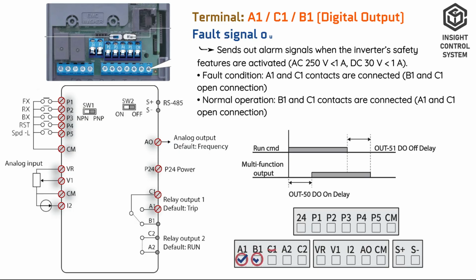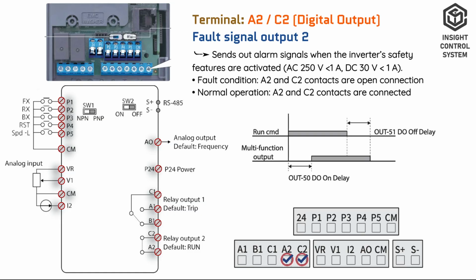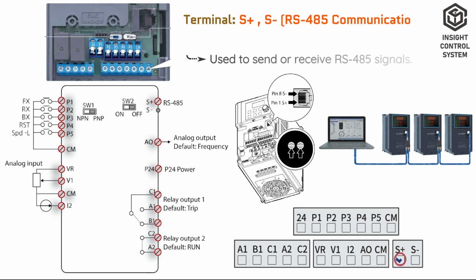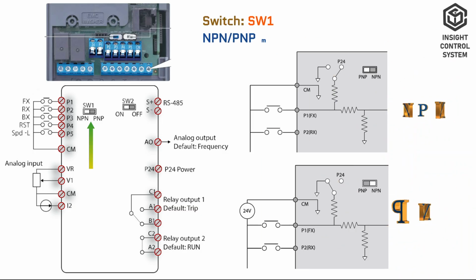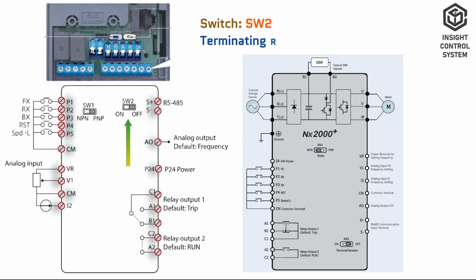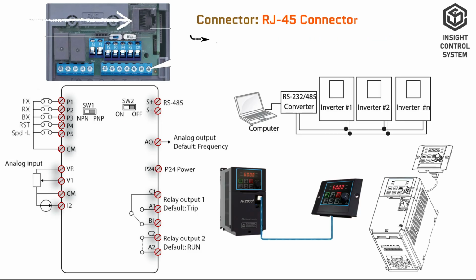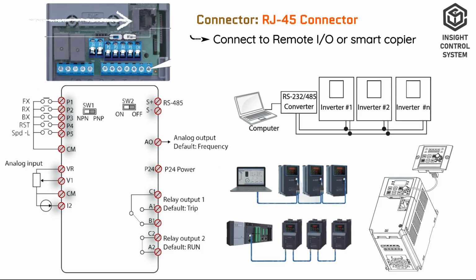A1, C1, and B1 terminals are digital outputs, indicating fault signal output 1. A2 and C2 terminals are digital outputs, indicating fault signal output 2. S plus and S minus is RS485 signal input terminal. This is switch 1, that selects either NPN or PNP modes. This is switch 2 for selecting the terminating resistor. This is RJ45 connector. It interfaces to remote I/O devices or smart copiers or RS485 communication.